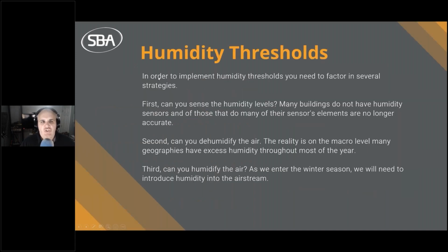All right. So, in order to implement these factors or thresholds, you need to factor in several strategies. First, can you even sense the humidity levels? I mean, if you don't have humidity sensors or they're not accurate, then that's the first thing you need to remediate. And I think you will see a lot of folks starting to take this seriously because humidity not only has a direct effect on comfort, but based on a lot of studies, it has a direct effect on virus mitigation. Second, can you dehumidify the air?